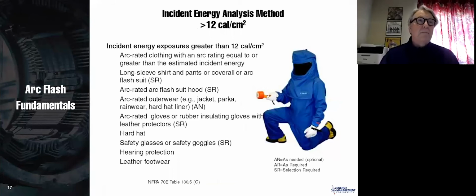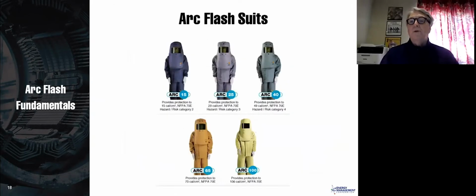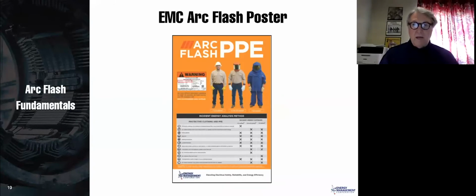Now, there is a second method for doing that. That's the PPE categories method, or what used to be called the hazard risk categories method. That's still a valid method, but we have typically changed to the newer method for all of our arc flash studies. But if you want to use the older method, you certainly can. These are some arc flash suits, and the highest rating that I know of for an arc flash suit is 100. I'm not saying that there might not be something higher, but that's the highest that I've seen.